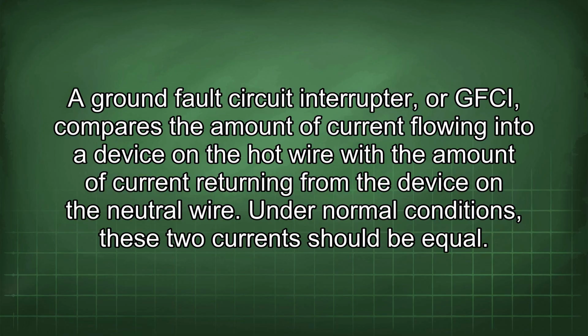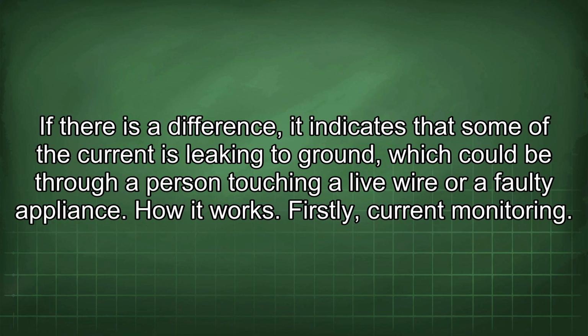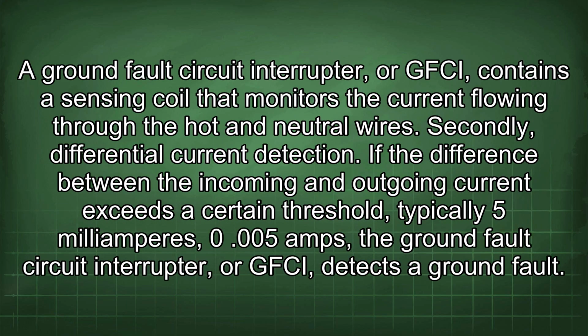Under normal conditions, these two currents should be equal. If there is a difference, it indicates that some of the current is leaking to ground, which could be through a person touching a live wire or a faulty appliance. How it works. Firstly, current monitoring. A GFCI contains a sensing coil that monitors the current flowing through the hot and neutral wires. Secondly, differential current detection. If the difference between the incoming and outgoing current exceeds a certain threshold, typically 5 mA, 0.005 amps, the GFCI detects a ground fault.